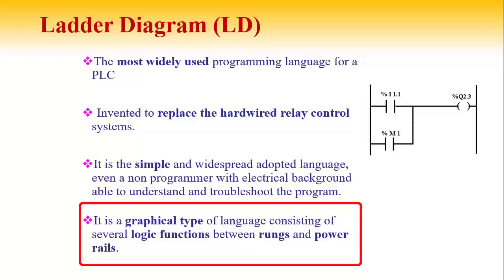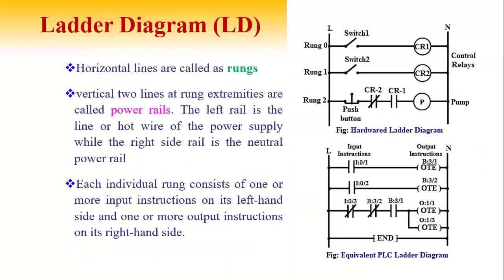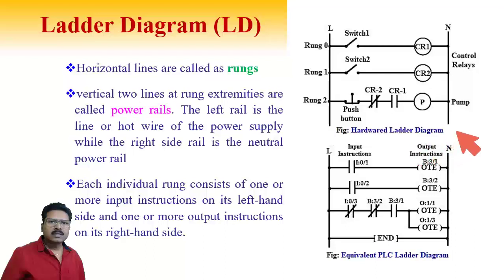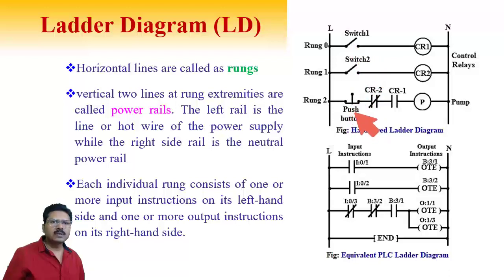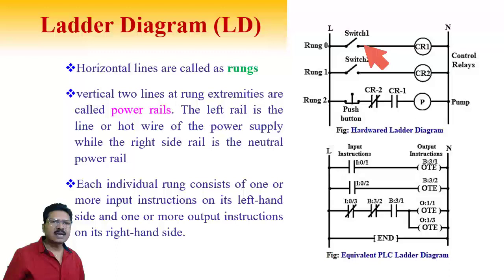Ladder is a graphical-type language consisting of several logic instructions, rungs, and power rails. To explain Ladder Diagram with a simple example: here is a hardware relay logic with three switches — Switch 1, Switch 2, and a push button. When Switch 1 is pressed, the pump turns ON (start switch). When Switch 2 is pressed, the pump turns OFF (stop switch). The push button may be used as an emergency stop switch.